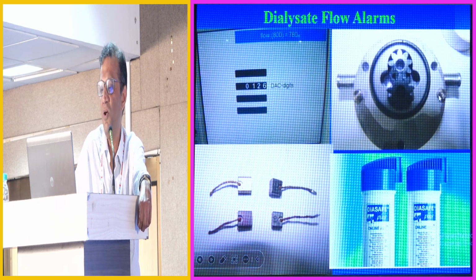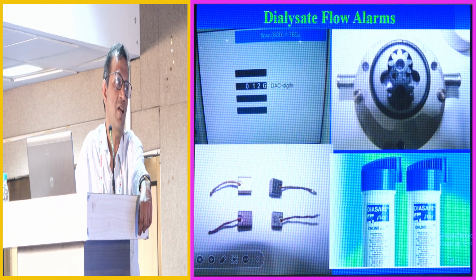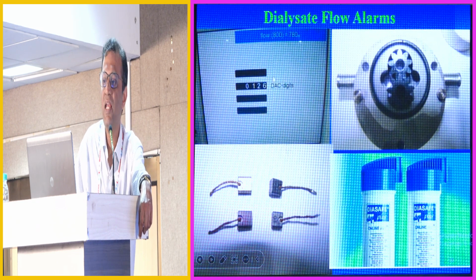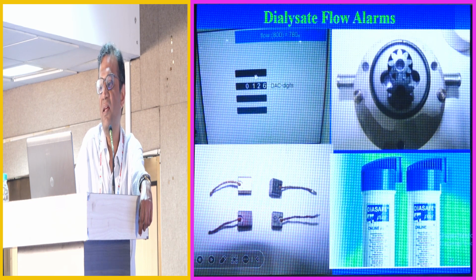Another cause is that the gears will tend to wear down with time. When the gears wear down, the machine will give a flow alarm, but this can be taken care of by increasing the rotations per minute, and that is done by increasing the digital to analog conversion digits in the calibration flow menu.